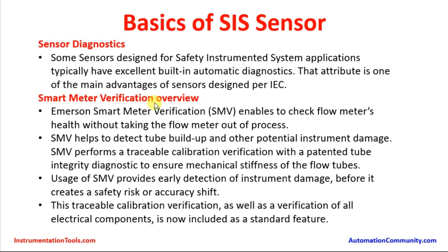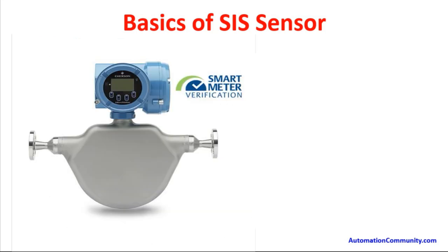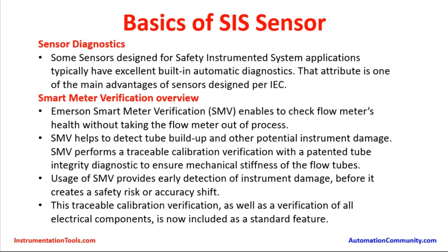Smart Meter Verification overview — this is provided by manufacturer Emerson. They provide an additional electronic board in the same sensor to ensure that diagnostics and the meter are functioning perfectly. This is used for some flow measurements and inline flow measurements, such as ultrasonic flow measurement transmitters. Smart Meter Verification, known as SMV, enables checking flow meters without taking the flow meter out of the process. In a 2oo3 voting setup, one sensor can be kept out by applying a necessary bypass in the system logic.